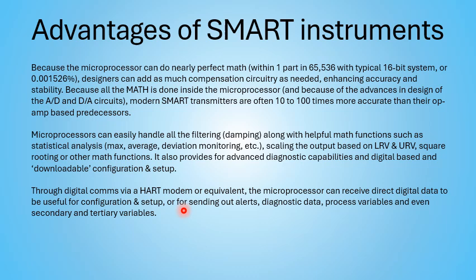Through digital comms via HART modem or equivalent, the microprocessor can also get data, so you can send it information. You can change the configuration without having to go up on top of the flare or whatever it is. And it can also send out those alerts, the diagnostic warnings, etc.